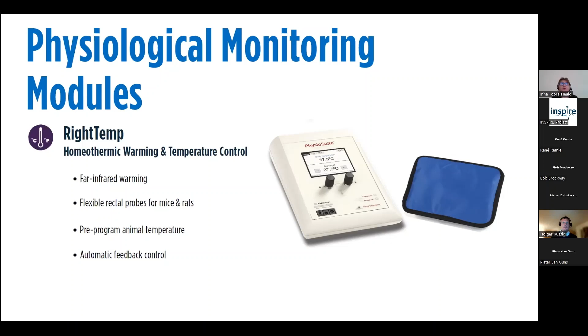Here, you see the RightTemp monitoring system with the pad. So the pad is attached directly to the face of the unit. And then the other 2 spots are for the probes. It's far infrared warming, so it warms directly through the tissue. The rectal probes are flexible for either rats or mice or any other small animal such as hamster, or chinchilla, or even the marmoset. You can pre-program the unit to reach the appropriate temperature, and if the temperature goes up or down, the unit will automatically correct it and bring it to the set temperature. You can also connect it to the computer for the automatic feedback control and record the measurements as well.